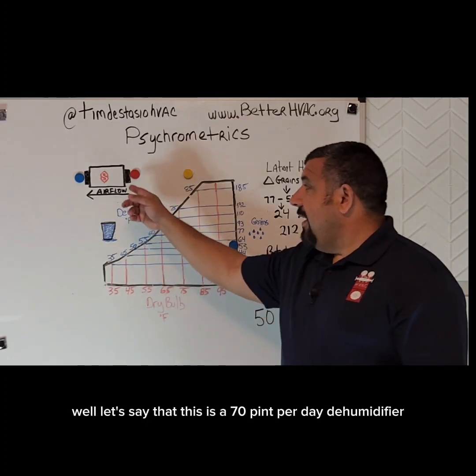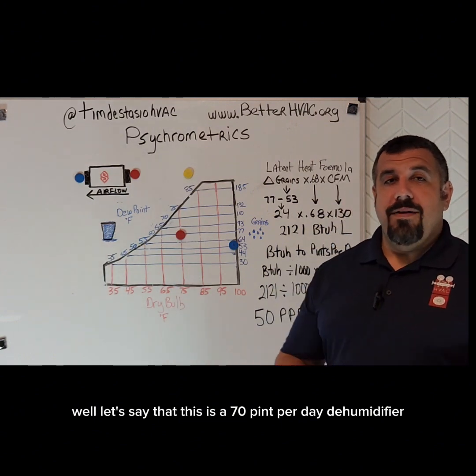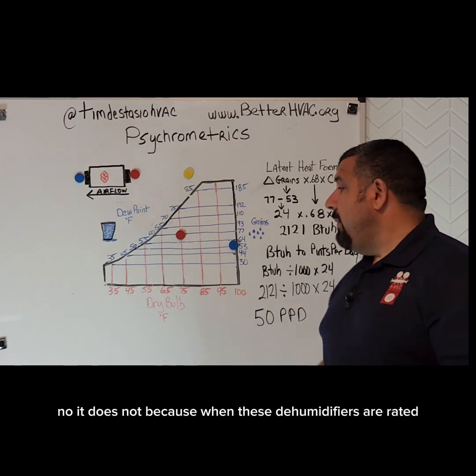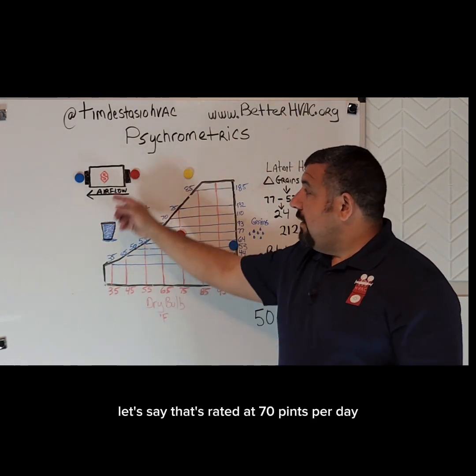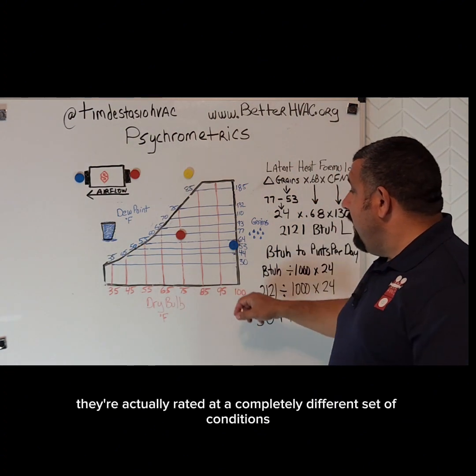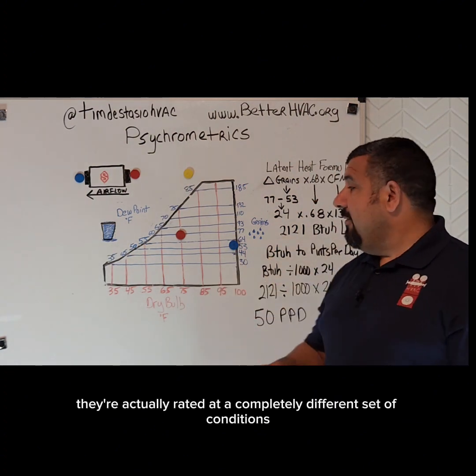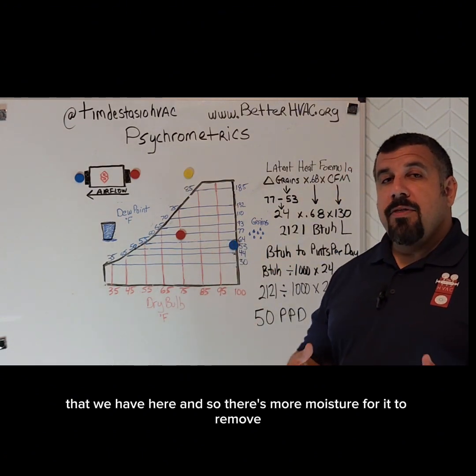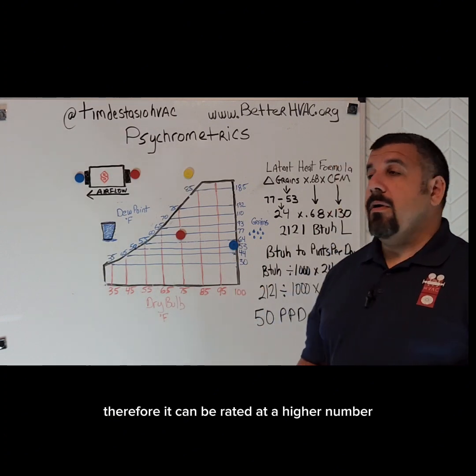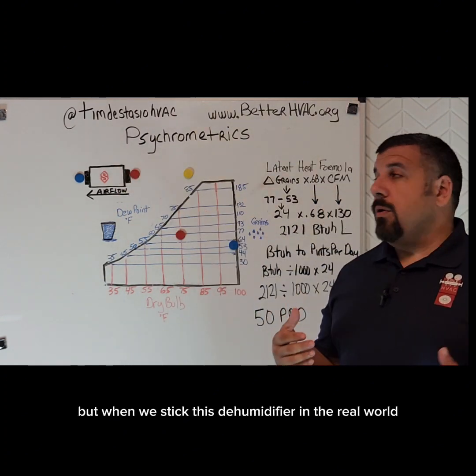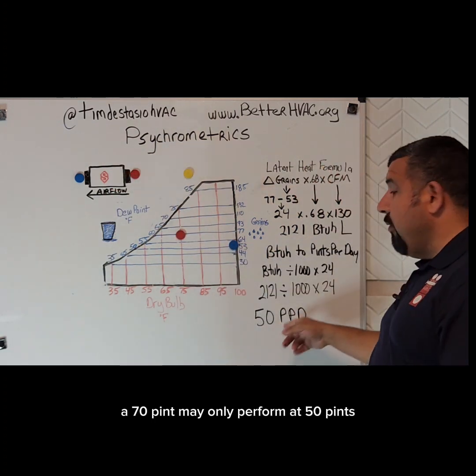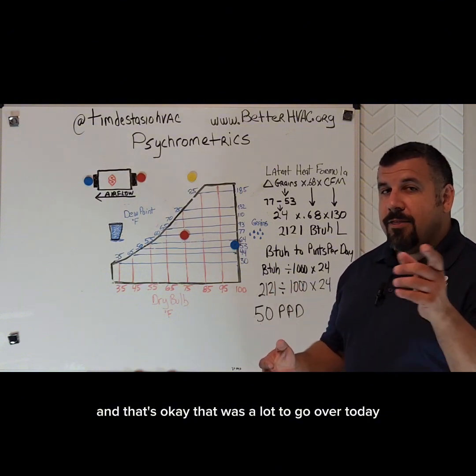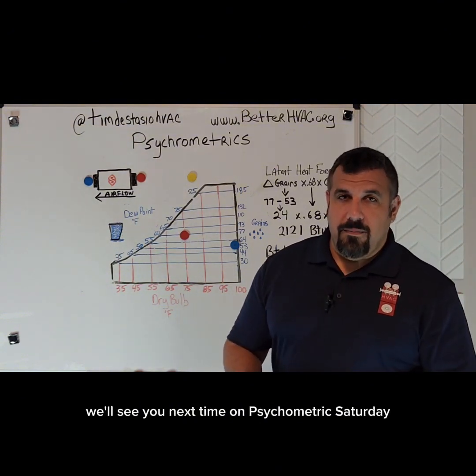Let's say this is a 70 pint per day dehumidifier. Does that mean the dehumidifier is not performing correctly? No, it does not. Because when these dehumidifiers are rated at 70 pints per day, they're rated at a completely different set of conditions — there's more moisture for it to remove, so it can be rated at a higher number. But when we stick this dehumidifier in the real world, a 70-pint unit may only perform at 50 pints, and that's okay. That was a lot to go over today. Thanks for your patience — we'll see you next time on Psychrometric Saturday.